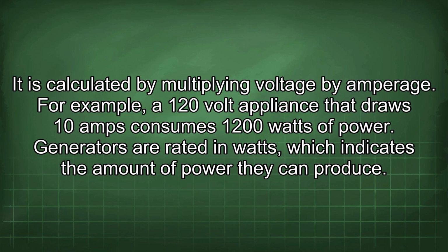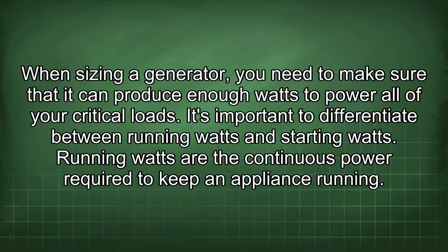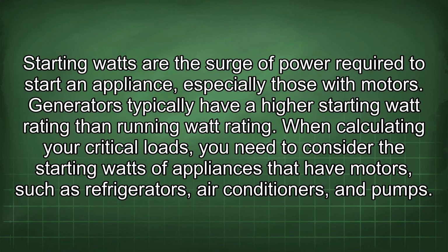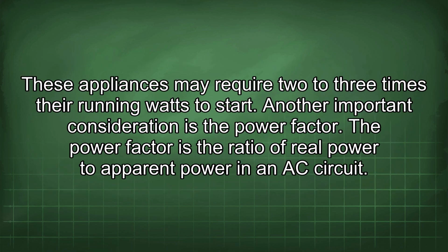Generators are rated in watts, which indicates the amount of power they can produce. When sizing a generator, you need to make sure that it can produce enough watts to power all of your critical loads. It's important to differentiate between running watts and starting watts. Running watts are the continuous power required to keep an appliance running. Starting watts are the surge of power required to start an appliance, especially those with motors. Generators typically have a higher starting watt rating than running watt rating. When calculating your critical loads, you need to consider the starting watts of appliances that have motors, such as refrigerators, air conditioners, and pumps. These appliances may require 2 to 3 times their running watts to start.